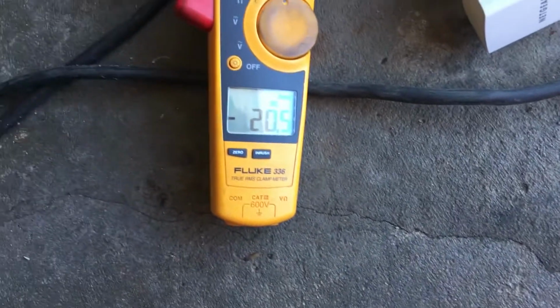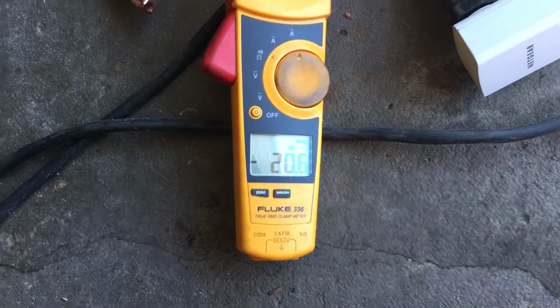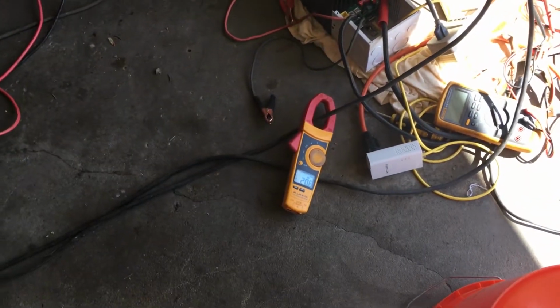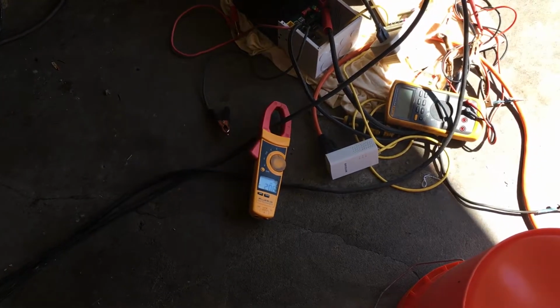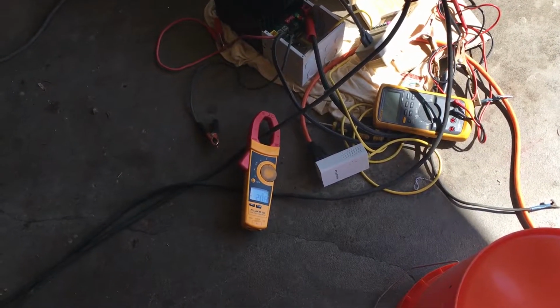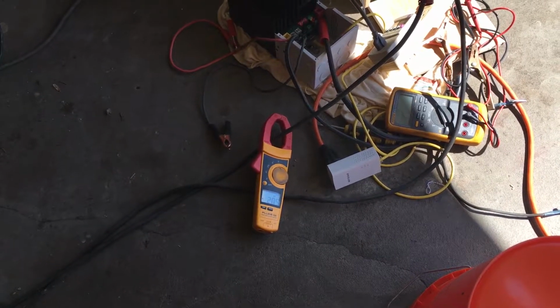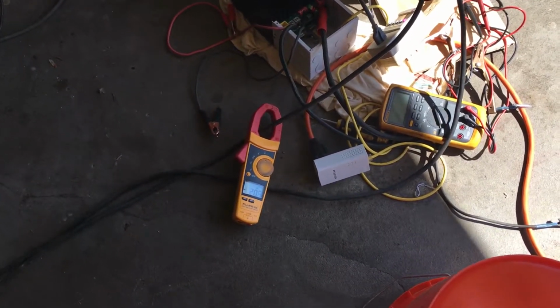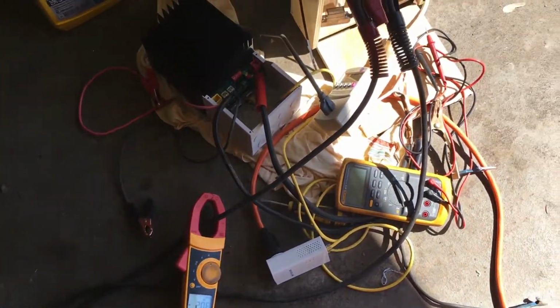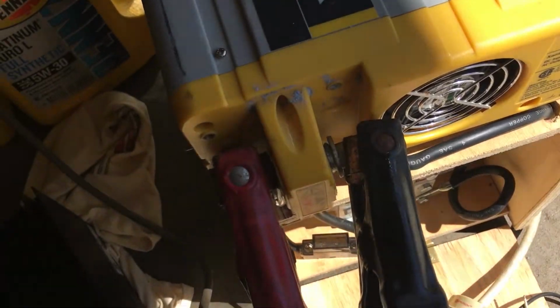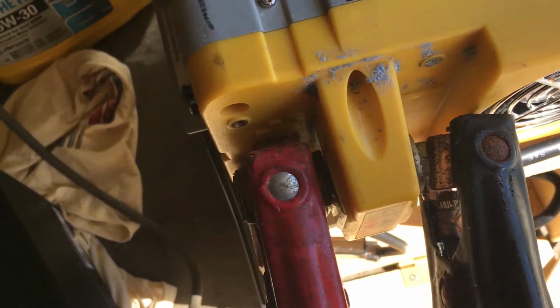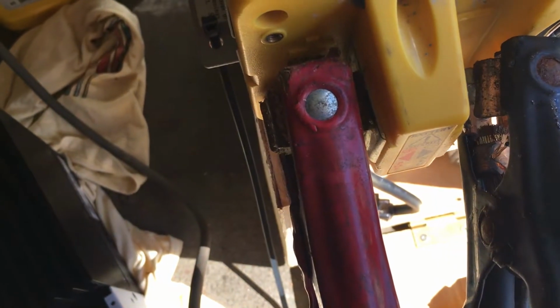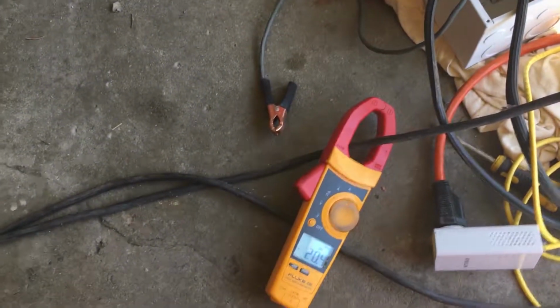So as you can see, we're pulling 20 amps right now. Take 20 amps times 24 volts, and that tells you how many watts you're putting through. I didn't know if it would go to 50 or 20 when I turned it on, and honestly I'm not sure why it's doing 20 instead of 50. It could have to do with how loose or tight these connections are that I'm clamping to, so I could try readjusting to get a better bite and see if that increases it.